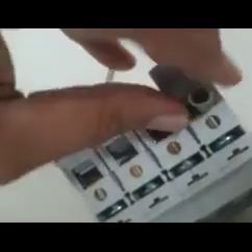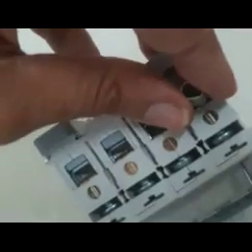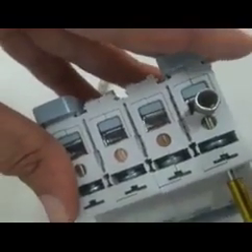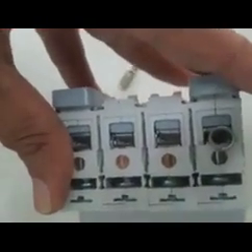You can use a lug to connect this MCB, or you can also connect a bare cable for proper connection. Let's see what happens when I use a lug here. When I am tightening this lug, which is a lug for 4 square mm, you can find there is some gap.